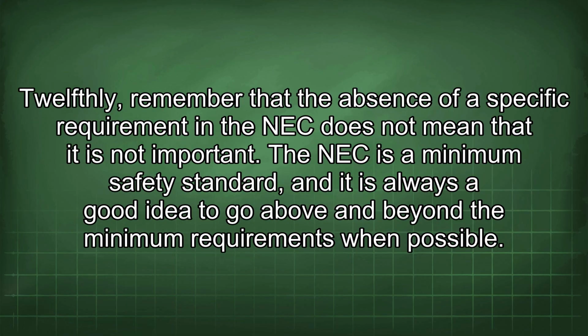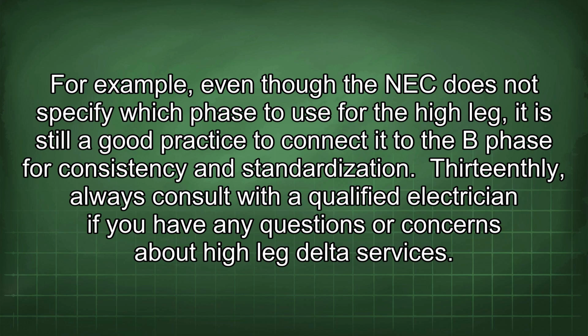12thly, remember that the absence of a specific requirement in the NEC does not mean that it is not important. The NEC is a minimum safety standard, and it is always a good idea to go above and beyond the minimum requirements when possible. For example, even though the NEC does not specify which phase to use for the high leg, it is still a good practice to connect it to the B phase for consistency and standardization.